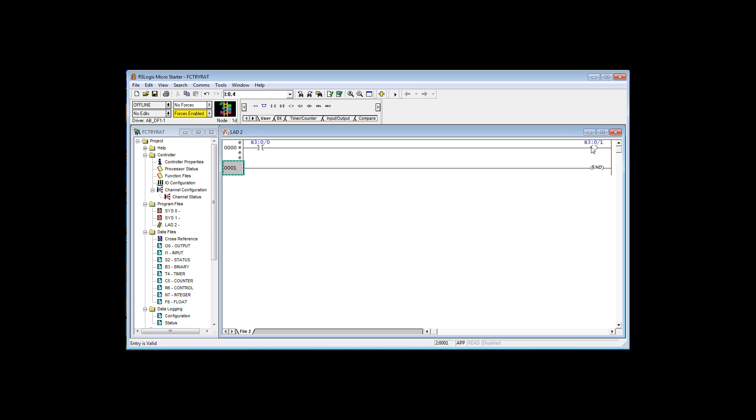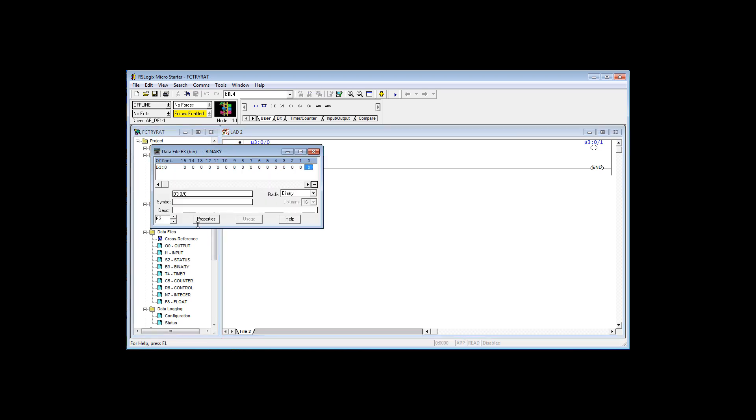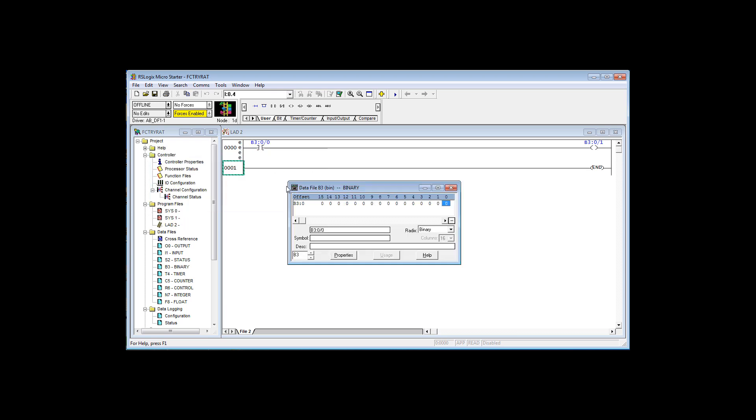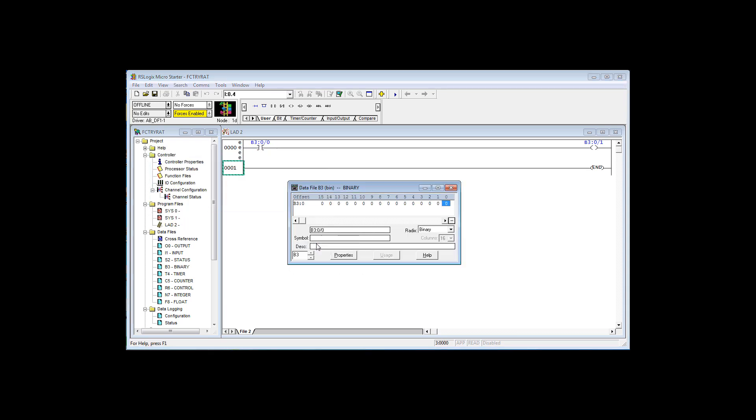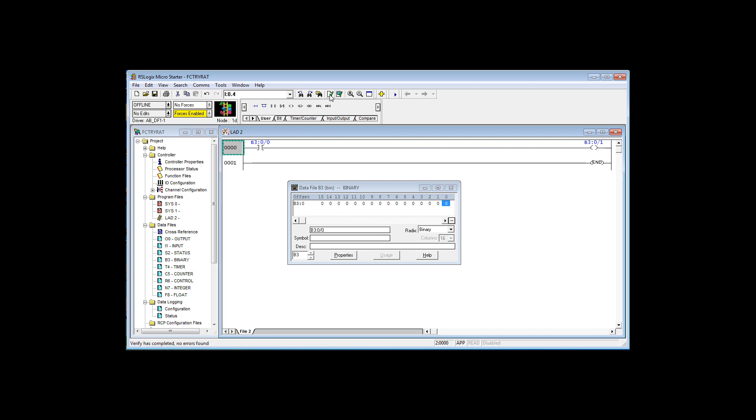Both of these bits of memory are in the same word. I'm going to double click on B3 here to bring it up. I'm going to lock it on top so it doesn't disappear. Now I'm going to finalize this, verify file. This rung says if B3 0/0 is on, then this is true. Energize this bit memory B3 0/1.